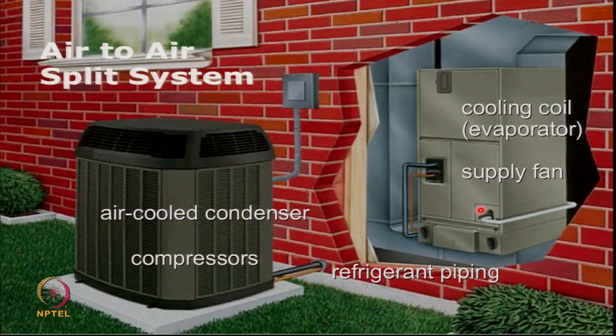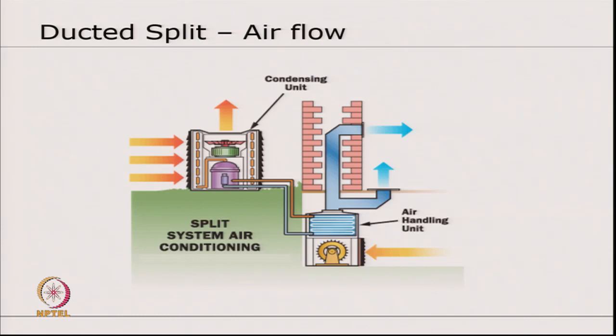This is an example of a ducted system. So a very large air-cooled condensing unit with compressors here, and then it's connected to a cooling coil and supply air fan, and then we see the ducts which would be servicing the home. Now here we don't have as much complexity surrounding distribution of refrigerant to different rooms and indoor units. In the ducted split, the airflow is something of this nature, and this example is actually more of a US home, where in the basement you have the indoor part of the air handling unit, and then it is directing the duct through different parts.